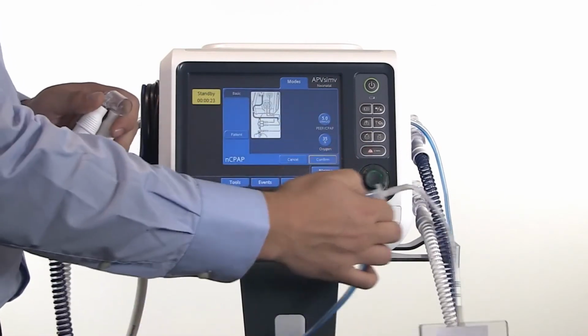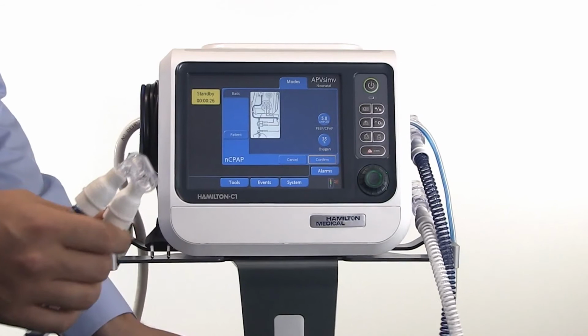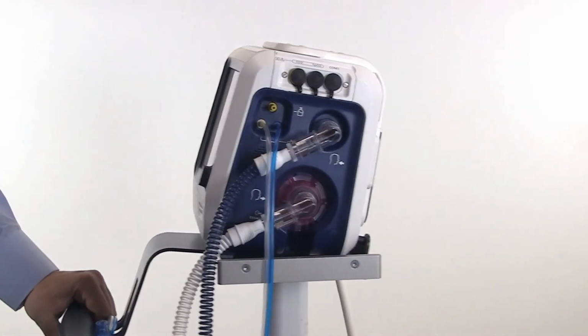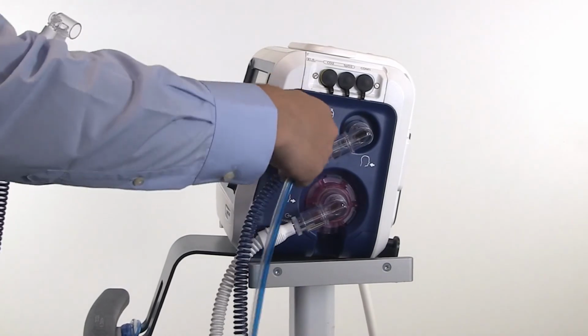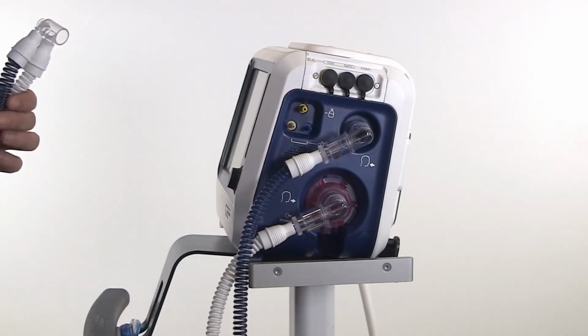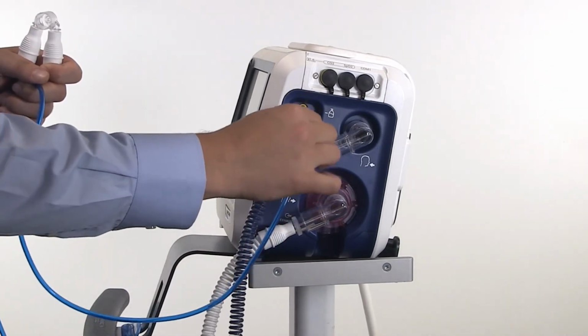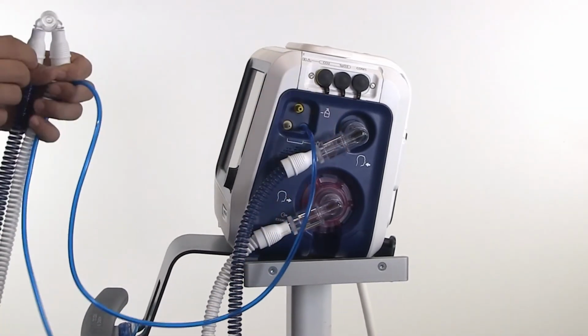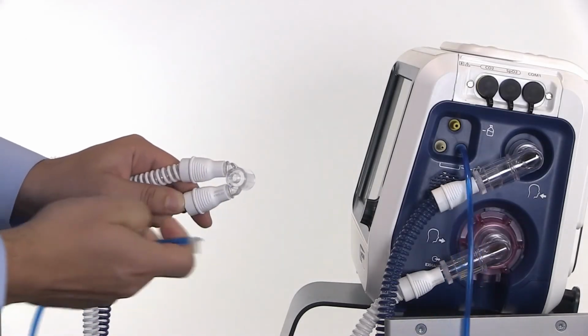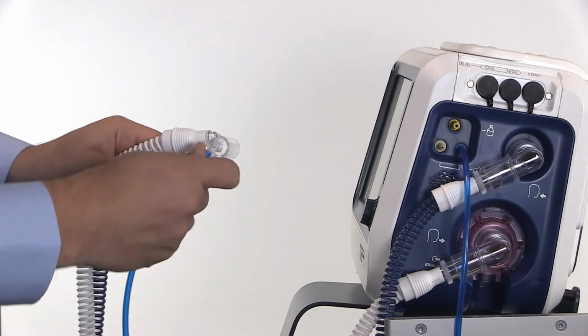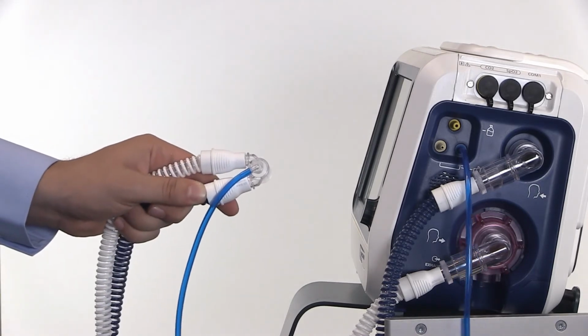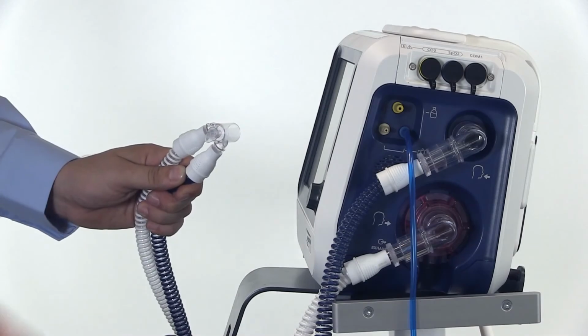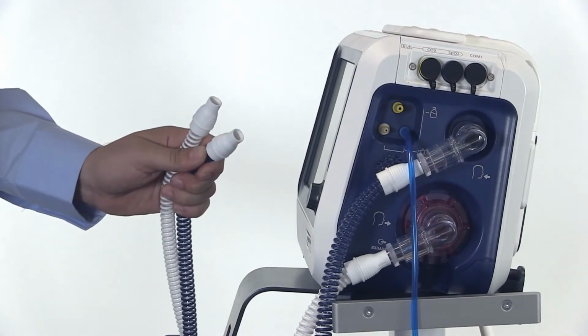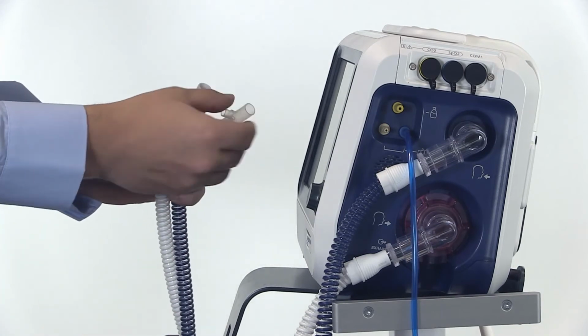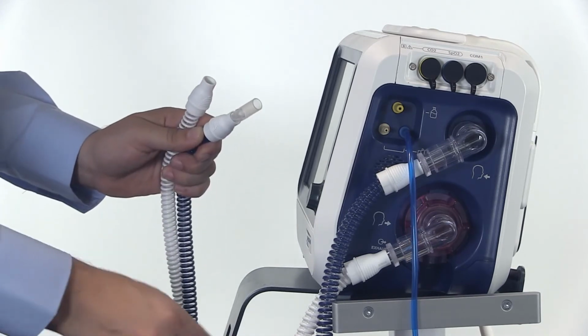Firstly, disconnect the flow sensor from the breathing circuit and the tubes from the ventilator. Then connect the pressure monitoring line to the ventilator. There are two ways of connecting the pressure line to the circuit. A. If using nasopharyngeal CPAP, you need to attach the pressure line to the Y-piece. B. If using binasal CPAP, remove the Y-piece, attach the T-piece to the pressure port of the inspiratory limb, and plug the pressure line into the T-piece.